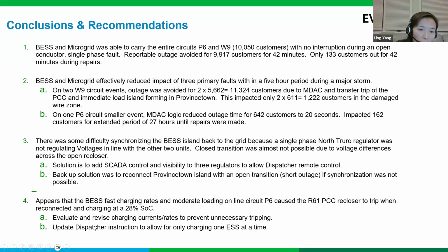And the other one is that when we were trying to charge the batteries, one of the charging rates was probably set too high, and the point of interconnection recloser opened, sensing the load was too high. So there are some optimizations and more training with the operators that need to happen.